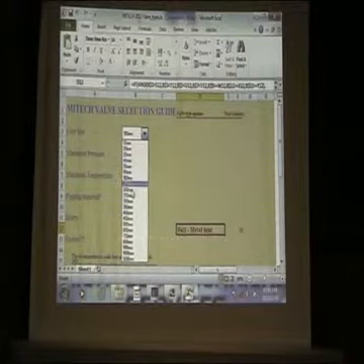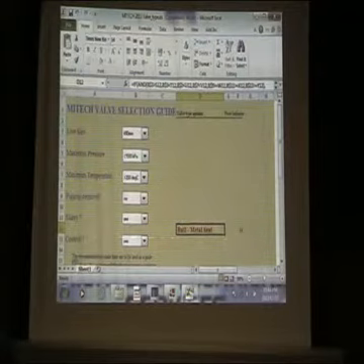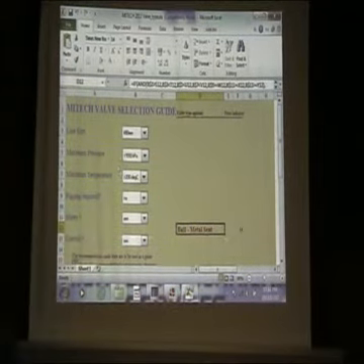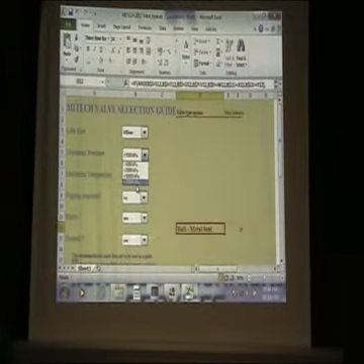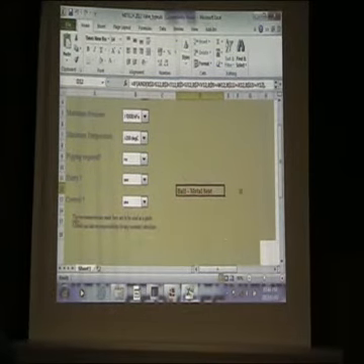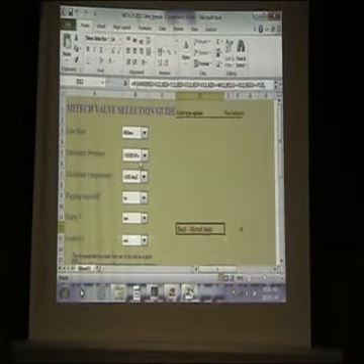Just one more quickly. Give me an example, anybody, any size. It's nice to play with this thing. 450. 450, alright. So we say the line size 450. Maximum pressure, let's go more than 10,000 kPa. Alright. Look where we now, we're already at only a metal seated ball. Okay, let's go to the low pressure stuff. Let's go less than 1000 kPa, less than 1000 degrees. There we're already on the butterflies, and we say it's not a slurry.